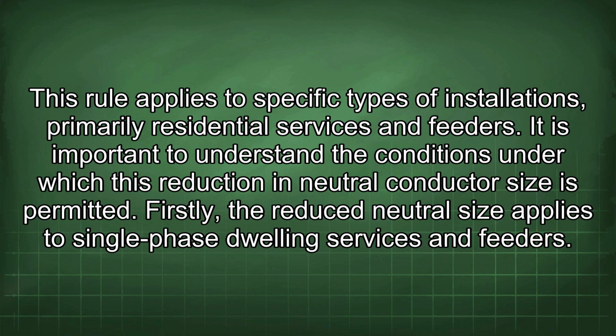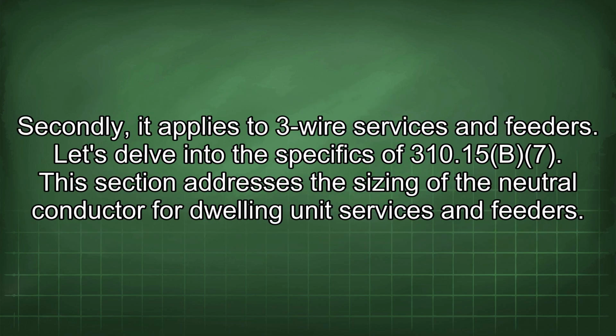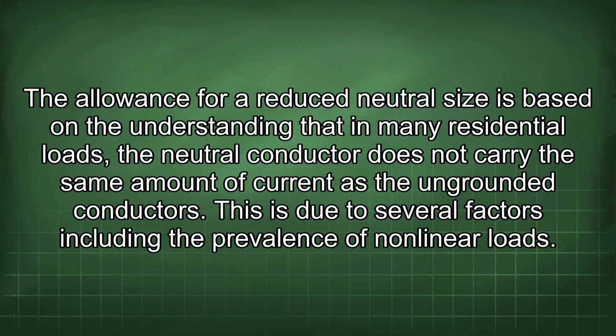Firstly, the reduced neutral size applies to single-phase dwelling services and feeders. Secondly, it applies to 3-wire services and feeders. Let's delve into the specifics of 310.15(B)(7). This section addresses the sizing of the neutral conductor for dwelling unit services and feeders. The allowance for reduced neutral size is based on the understanding that in many residential loads, the neutral conductor does not carry the same amount of current as the ungrounded conductors.